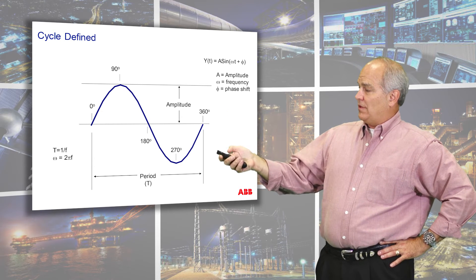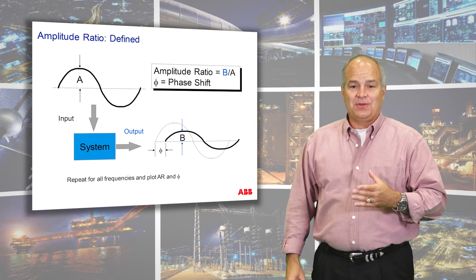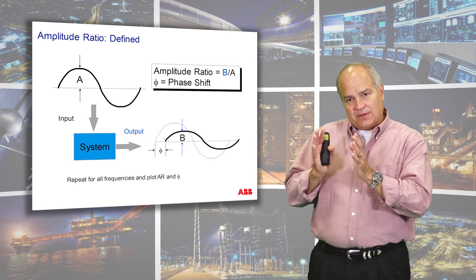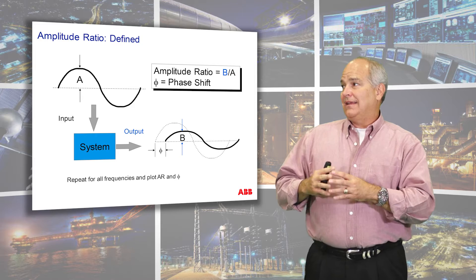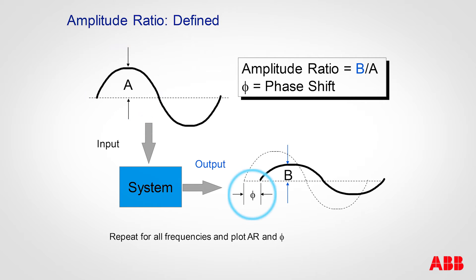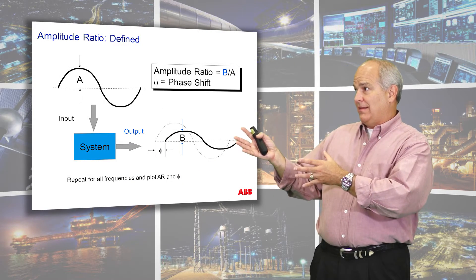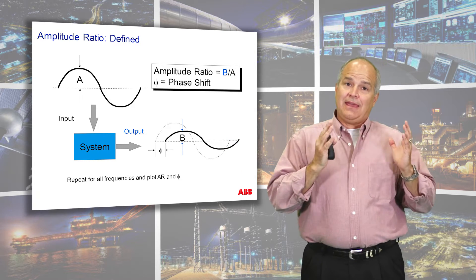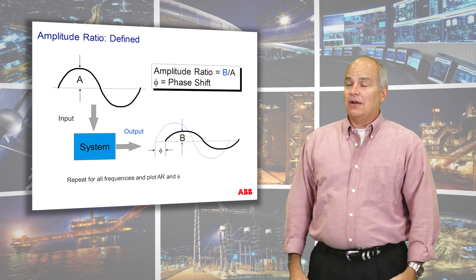When we look at a sine wave with an amplitude and it goes into a process, it comes out attenuated — well, we hope so. In tuning, we could actually make it come out worse. So in this first part of the video we're going to talk about what in the technical term is a Bode plot, but we're going to refer to it as an amplitude ratio. We have a system where the amplitude comes in with, let's say, A, and it comes out phase shifted with an amplitude B. The ratio of the amplitudes on the input and output of our process is what we refer to as the amplitude ratio.